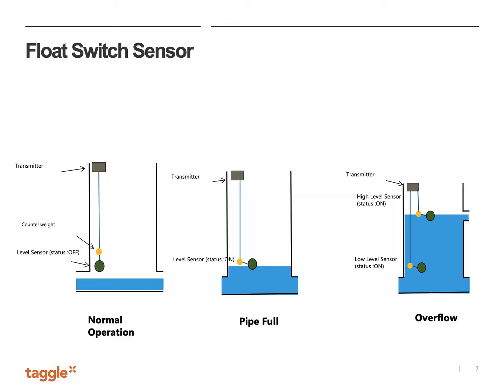In our very first generation of this, installed a few years ago, one of the things that we learned is that sewer networks, particularly in high rain events, can be quite turbulent environments. And these float switches don't smoothly transition from off to on. What they do is they bounce around, both due to water pressure and waves in the water, but also turbulence in the air. And our very, very first generation of these float switches sent the transmitters flat because they were transmitting every time that there was an event occurring.